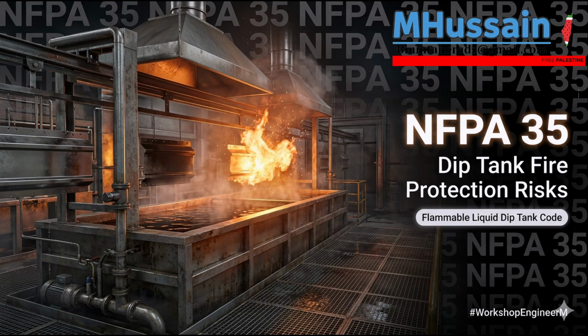Which, by the way, is a temperature easily reached within minutes during a solvent pool fire. Steel loses about 50% of its load-carrying capacity. 50%? In minutes? Yes. It begins to plasticize and buckle. And if those steel legs buckle, that 5,000-gallon tank collapses, instantly rupturing and dumping its entire massive payload of fuel directly onto the fire. Which just multiplies the disaster exponentially. Exactly. So how do the layout engineers and the contractors actually protect that steel?